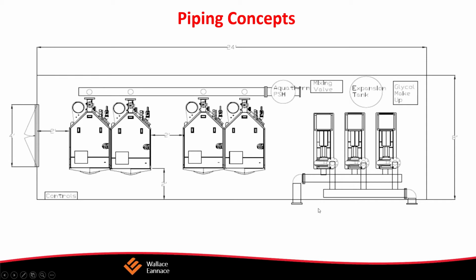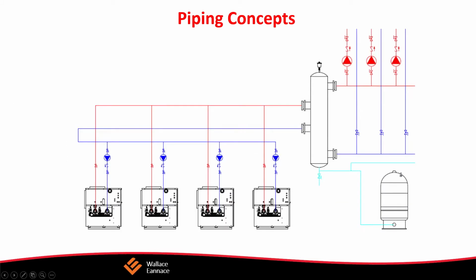Here's another application, same thing. Notice the expansion tank is tied in to the base of the primary, secondary header, and all the pumps are now pumping away from the expansion tank.